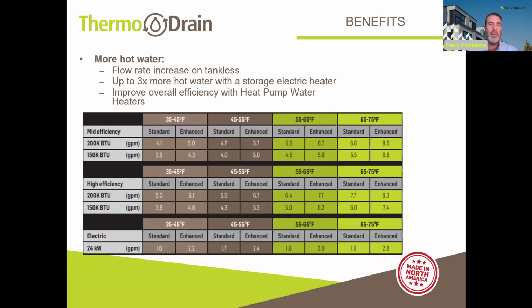If we have an electric storage water heater, which is popular in some portions of the country, and now with electrification coming around, might be more and more seen throughout new construction, we essentially are capable of increasing the capacity of the storage electric water heater by threefold. Having that preheated water coming into the cold side of the water heater obviously increases the inlet temperature significantly, so the electrical element doesn't work as hard, and you're basically having 3 times as much hot water. So that's of interest also.